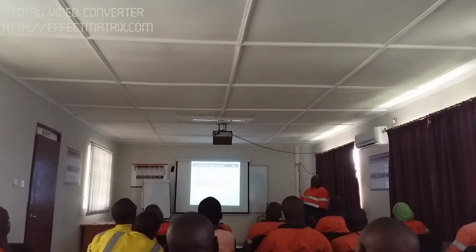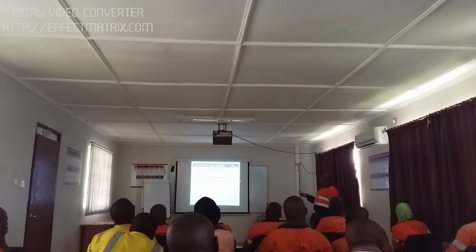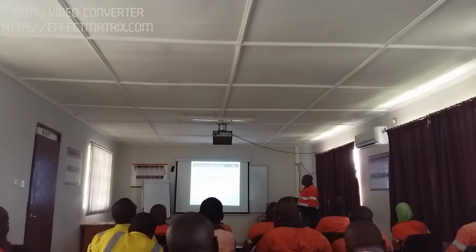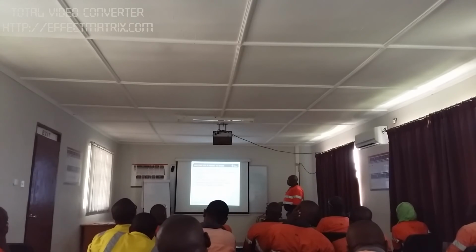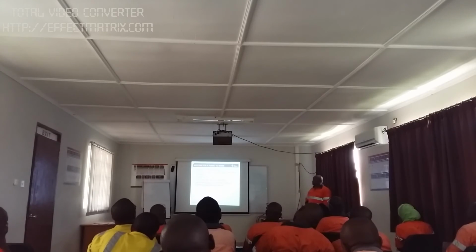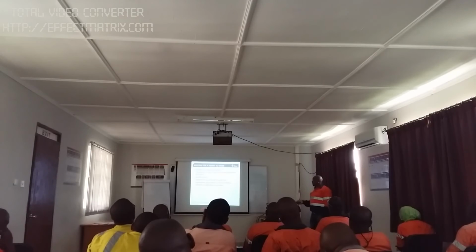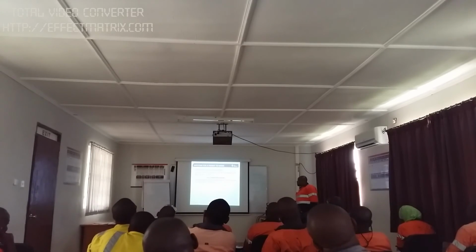Then we have the location of the lock boxes. This now depends on the type of isolation. So if it's a single point isolation, the document pack is kept by the permit requester at the job site for review by any safety or management representative. The following documents make up document part 4, the lockout tagout system: the job safety analysis, original white page for master isolation permit, original white page for other permits, hot work or confined space, as applicable. So which copy goes to the field?